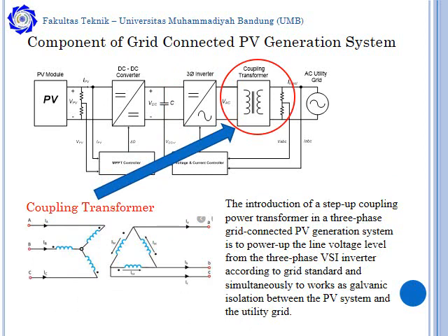Another component of the system is the coupling transformer. The introduction of the step-up coupling power transformer in the 3-phase grid-connected PV generation system powers up the line voltage level from the 3-phase voltage source inverter according to grid standard and simultaneously works as a galvanic insulation between the PV system and the grid.